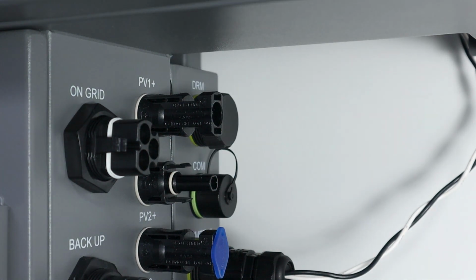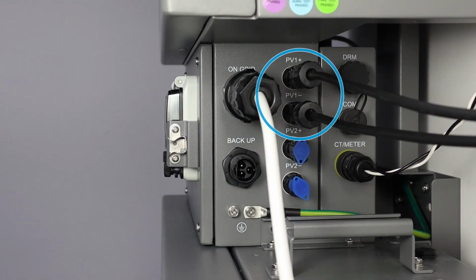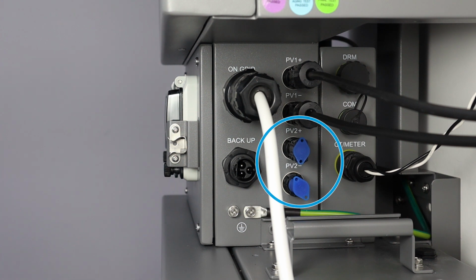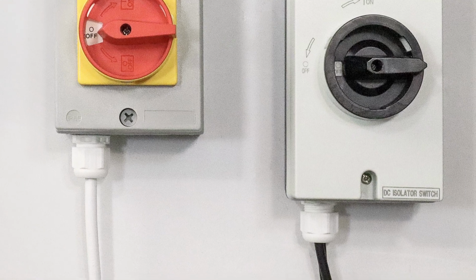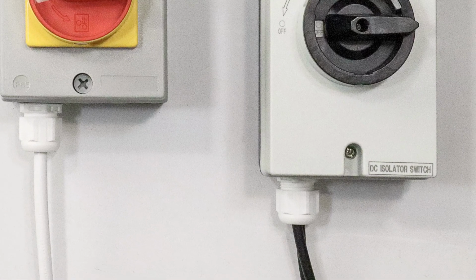The PV1 connection sockets are in the central bank of sockets and should be used for a single PV solar array. The inverter is also equipped with the capacity for a second PV solar array using the positive and negative PV2 ports. This PV connection should always be made to your PV array via a DC isolator switch.